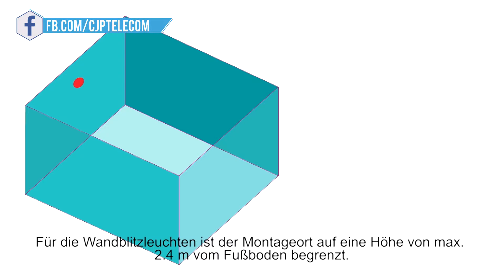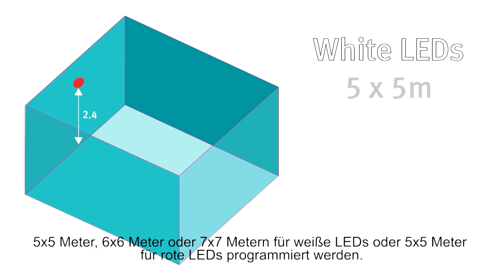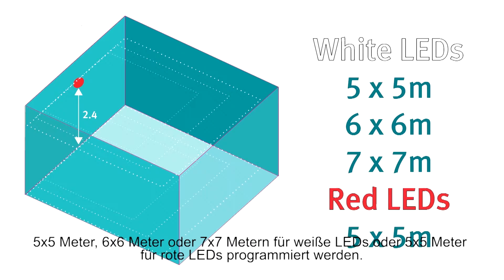For the wall beacons, the coverage volumes are based on a maximum height of 2.4 meters from floor level, so again subject to your control panel, you can set the coverage to 5x5, 6x6 or 7x7 meters for white LEDs and 5x5 meters for red LEDs.